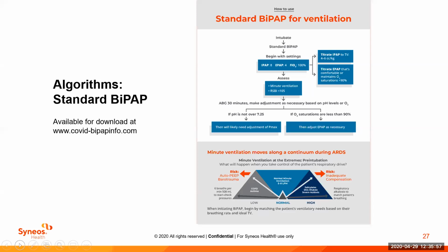Yes, in the previous mode, the AVAPS mode, we're targeting a tidal volume, and the machine is going to adjust pressure in order to aim to get that tidal volume sought after. In the BiPAP mode, this particular device, the IPAP and EPAP, for those of you that are familiar with the big mechanical ventilators, the driving pressure is different for these BiPAP devices or these non-invasive ventilators than it would be on the invasive ventilators. Driving pressure on this is typically the difference between EPAP and IPAP. So if I have my IPAP set at 8, my total pressure delivered to the patient is going to be 8 centimeters of water pressure. My drive pressure is then going to be 4 centimeters of water pressure. If I had this on a regular critical care ventilator, the total pressure on the regular critical care ventilator would be 12 centimeters of water pressure.